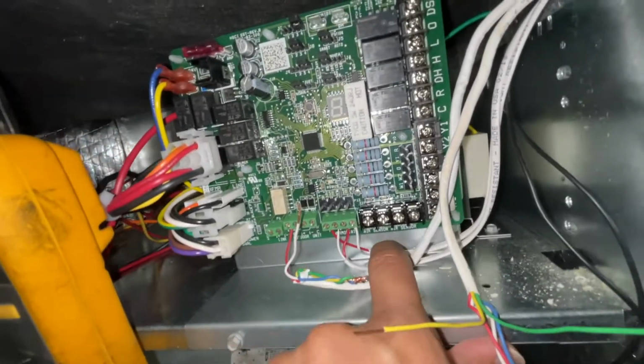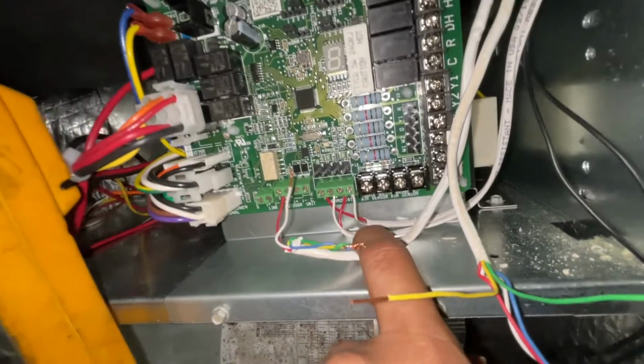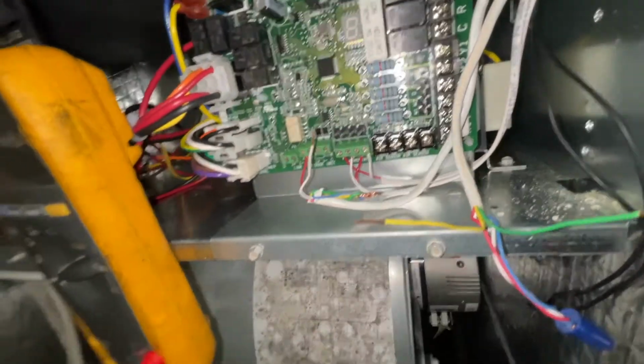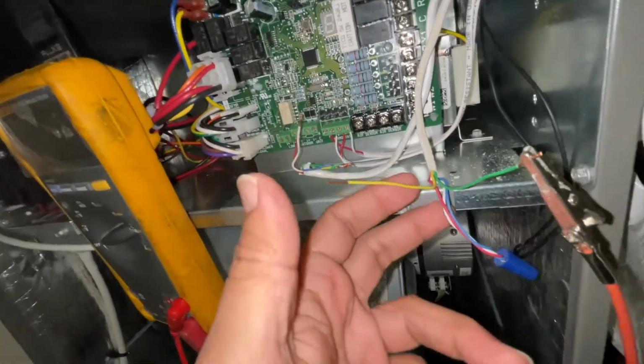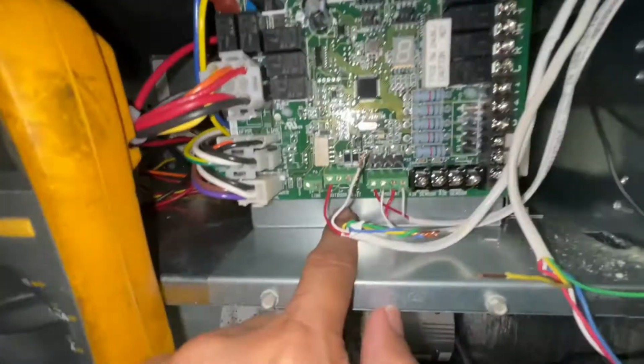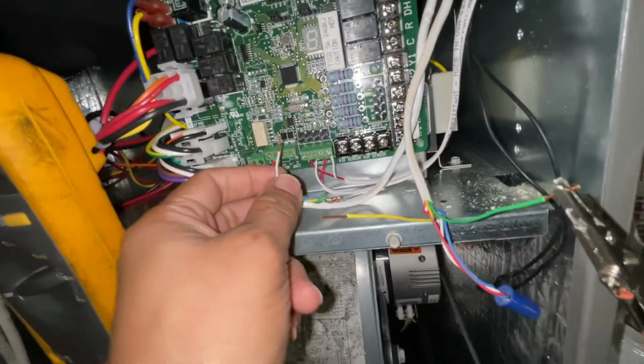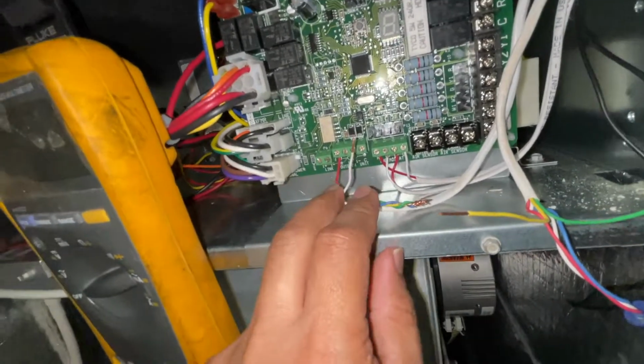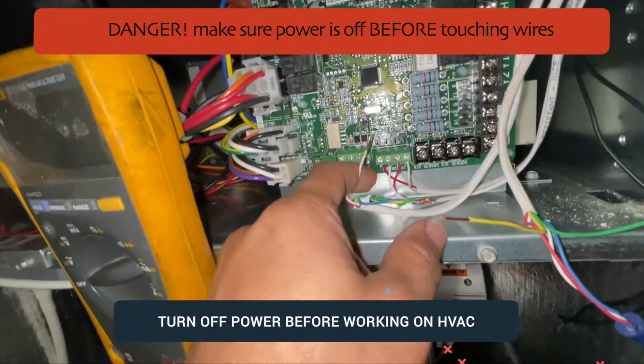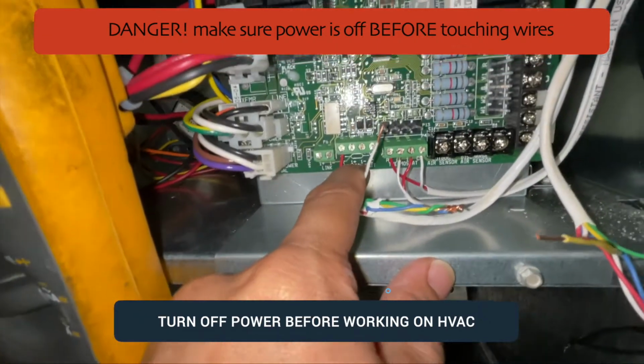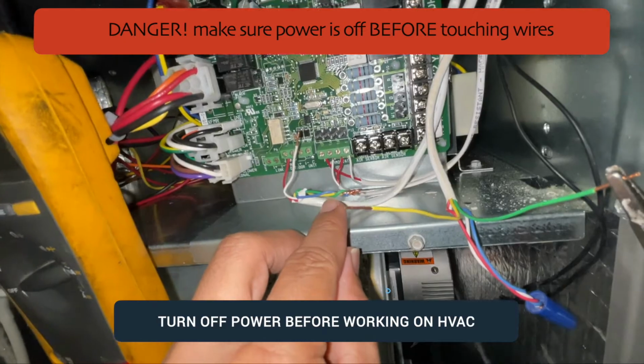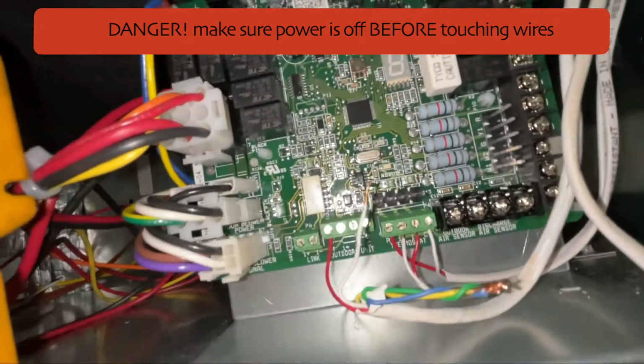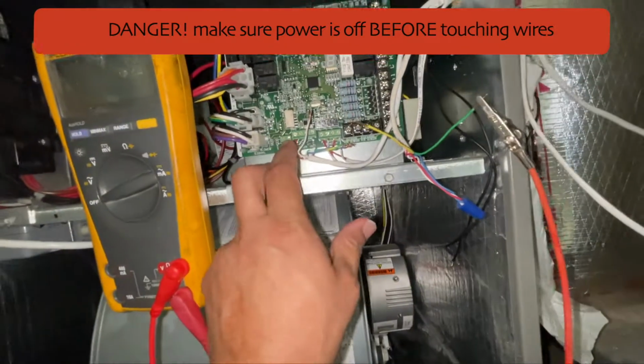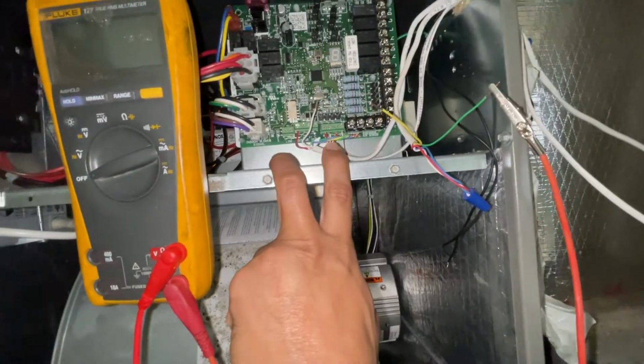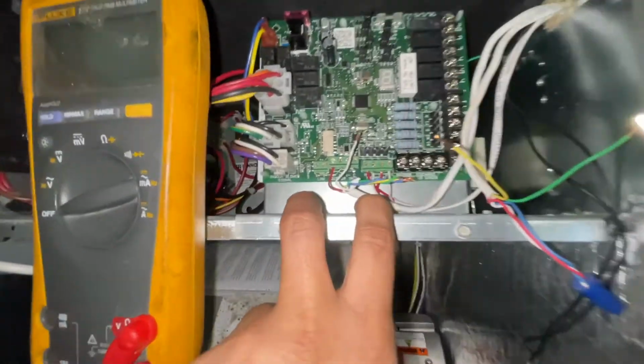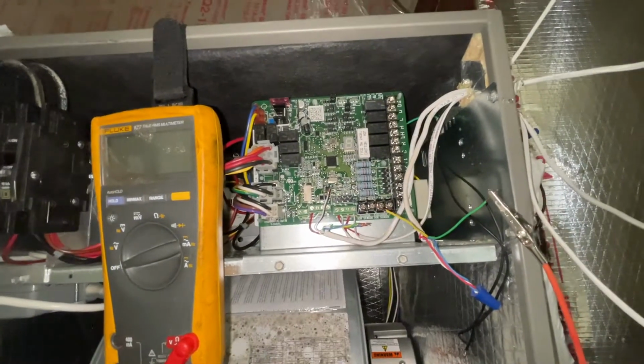I want to keep it separate in case there's any transient on this line. I don't want it to be affecting the other wire. So I kept them separate. If it's shielded, you can use the same one. Now this wire is going all the way out to the outdoor unit. This wire is not shielded, and one of the ways I tested this was I had the red one over here, the white one was at common, and then I had I minus and I plus, and those two wires were yellow and green. One of the things I noticed was I had high voltage AC on these communication lines. You're not supposed to have high voltage AC, and I was getting about 25 to 30 volts AC.